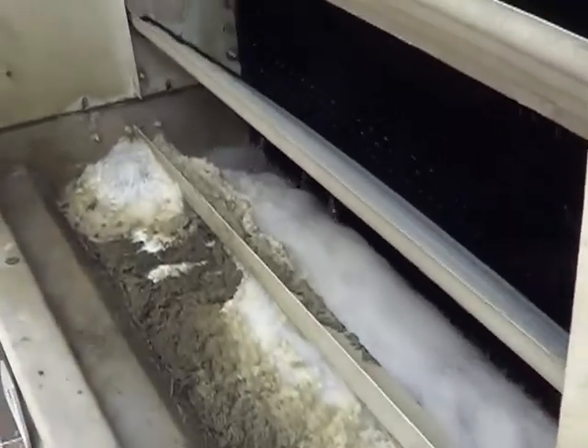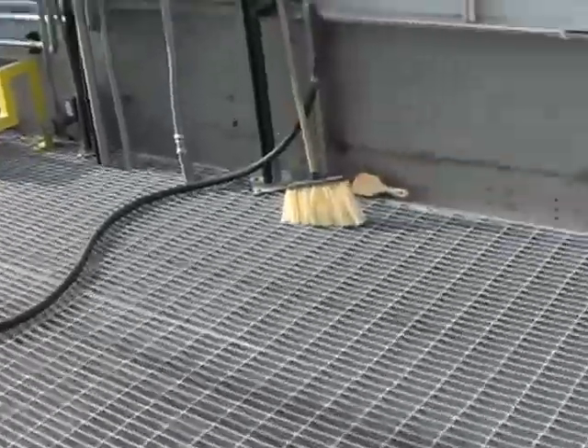Here's the troughs here. All that nasty foam, which seems when you keep your chlorine level up, you get more of this foam. And of course, it's a year-round problem that you have garbage in here. You got Legionella. You got every kind of nasty. If you got allergy issues, you probably couldn't do this job. And even if you don't, this stuff makes you feel pretty crummy for a day or so after you get in here and clean it out. Same thing on this side.